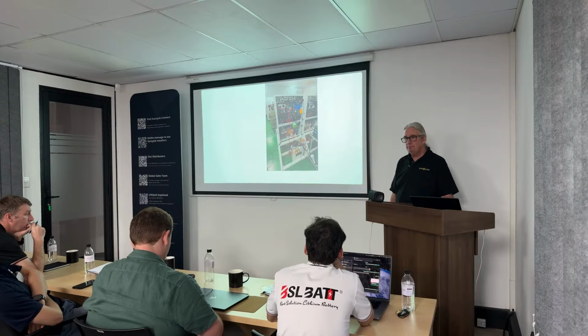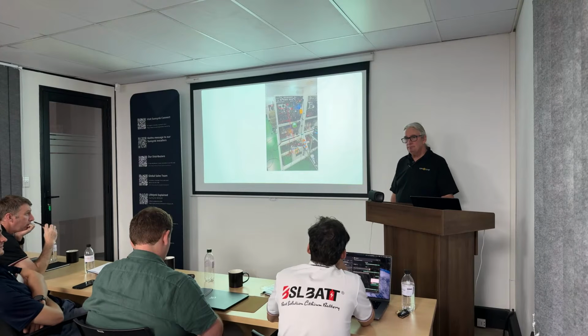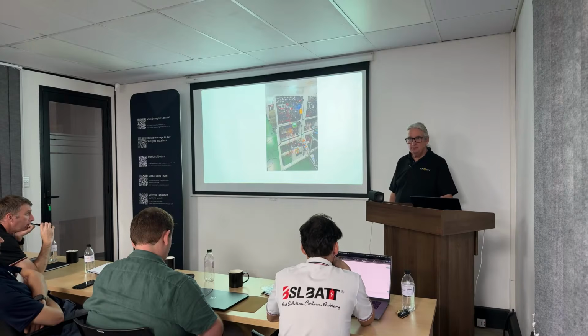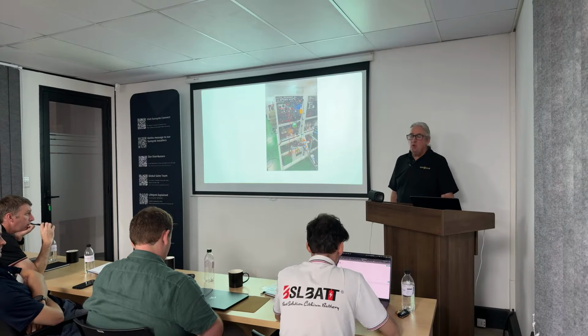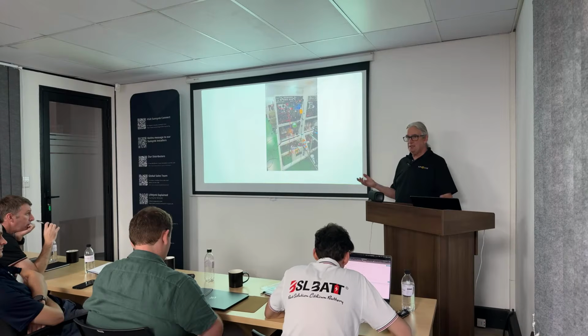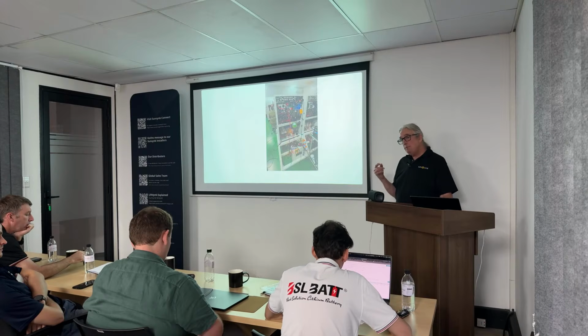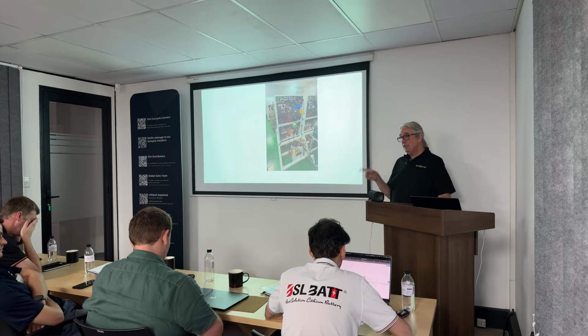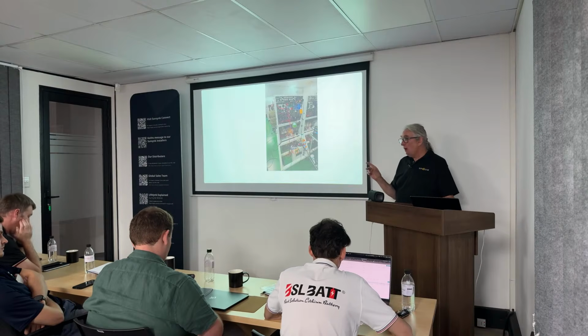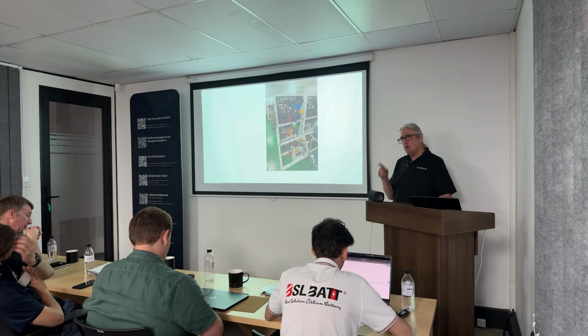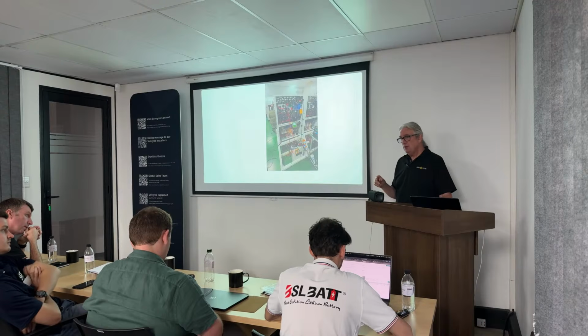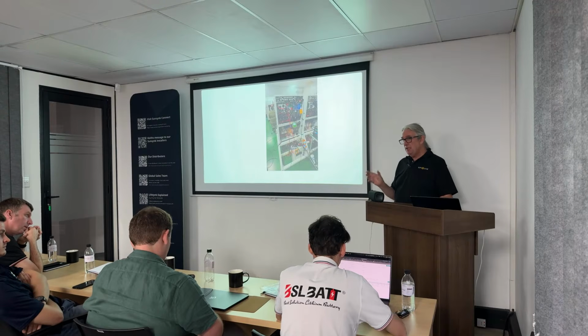And still, you've got two battery channels? Yeah, so still no common DC bus in the hybrid inverters - on our PCSs there's a common DC bus, so they can be common DC bus or single DC, you can do it either way. On the PCSs you can have them as separate channels or common DC bus, so it can be run either way.